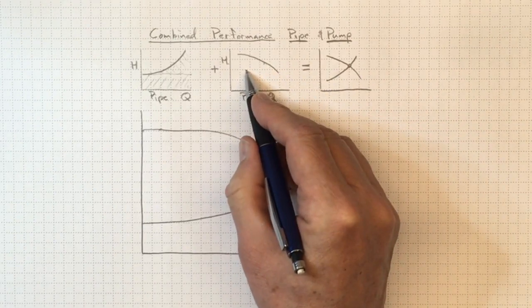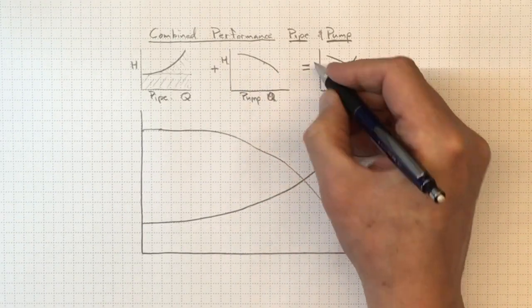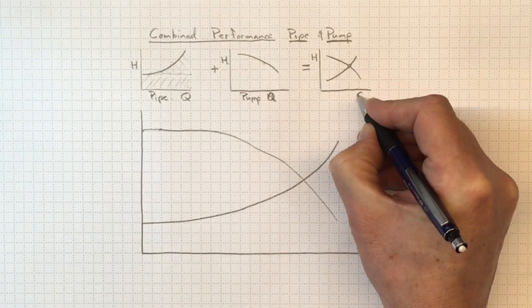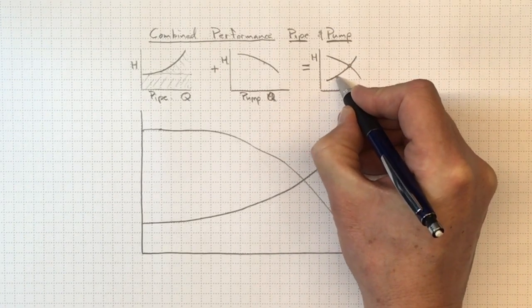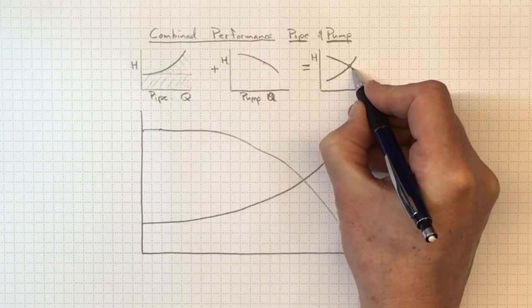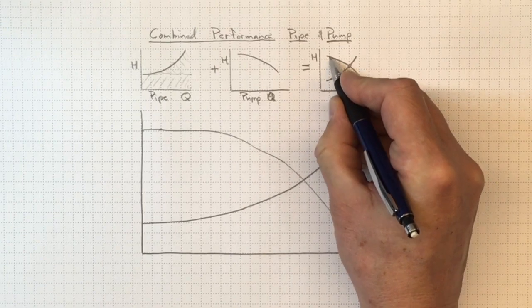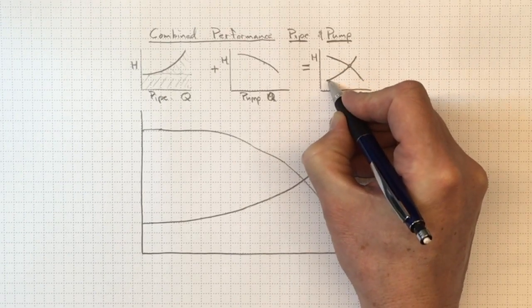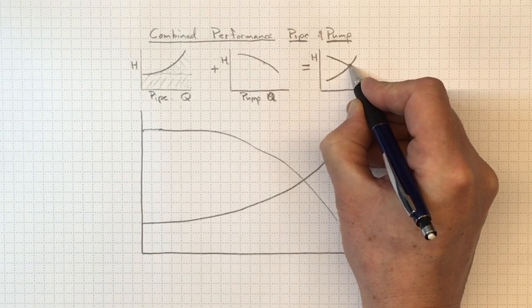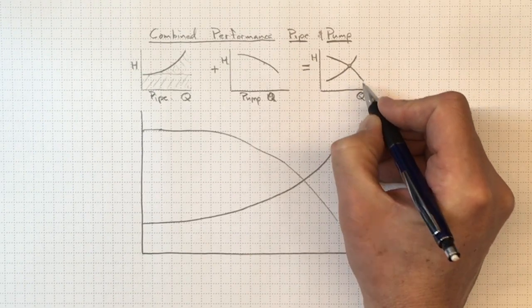And the two of them combined together, we can put on the same axes and find the intersection point between these two curves. If this is what the pump can do and this is what the piping requires, then where those two lines cross is the point where things will actually operate.